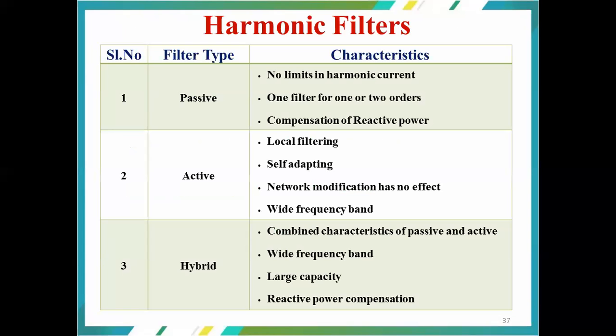There come the fire issues also. So when it comes to the elimination of these harmonics, these are all the types of filters: the passive filter, active filter, and the hybrid filter. The passive filter means we are going to construct the filter based on passive components, and in case of the active filters, we are going to construct the filtering components based on active components. Hybrid means we are going to combine the advantages of both passive and active.